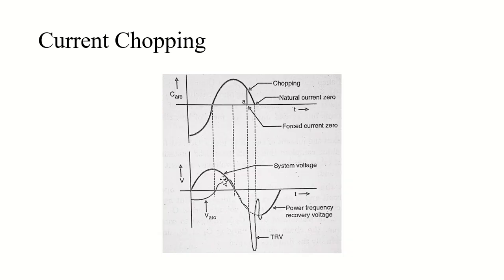The deionizing effect, still in action, will produce a second current drop and the value of this current will be smaller than the previous one. Again the restriking voltage will build up with some high RRRV, appearing across the contacts unless the arc continues. If the arc restrikes further, successive chops may occur before final interruption — the circuit breaker may fail to clear the fault. If restriking does not occur, a very high voltage appears across the contacts and will damage the equipment.